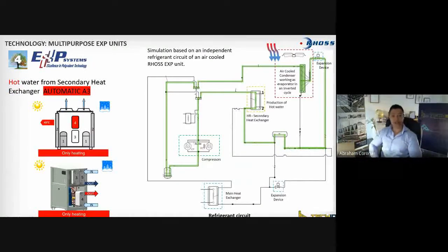Finally, but not least, we have automatic mode. If you remember, we have satisfied the demand of cooling, we have satisfied the simultaneous demand of cooling and heating. But it could be the scenario that in winter, I only want heat for the heating of the room. For any reason, I don't need cooling. So in that moment, I satisfy the temperature of my tank. The controller says, I don't need to use any more cold water, so I only need to produce heating.